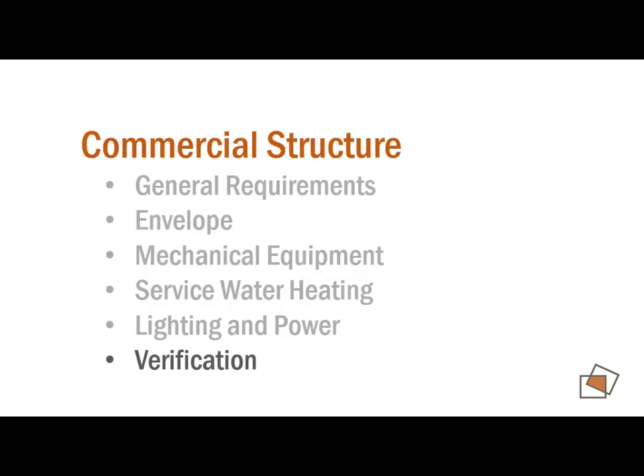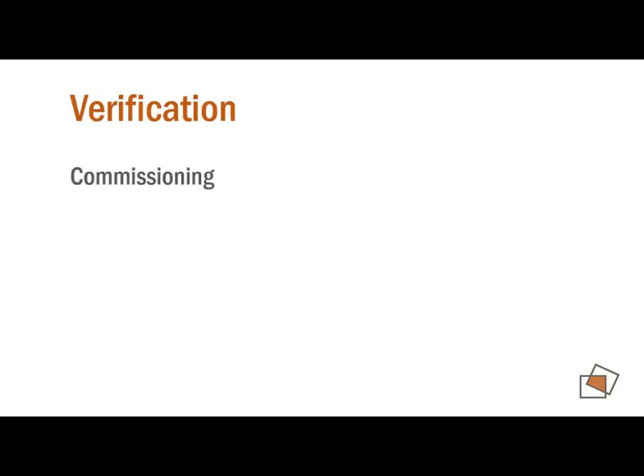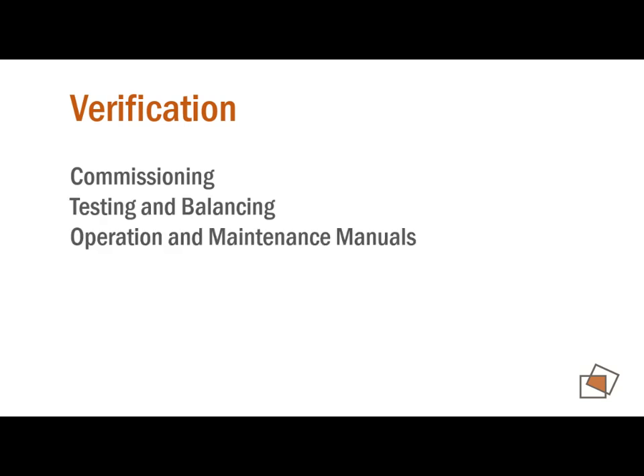Okay, so we've gone through the requirements of the energy code. Our bottom line here is the verification piece. There are three parts associated with the verification. First is the commissioning. The codes are going to require commissioning, then testing and balancing, and then providing O&M manuals to the owner. Testing and balancing is something we've done forever, and getting our own O&M manuals is standard practice. The commissioning is the new piece, and 2012 was the first time that it made an appearance in the code.